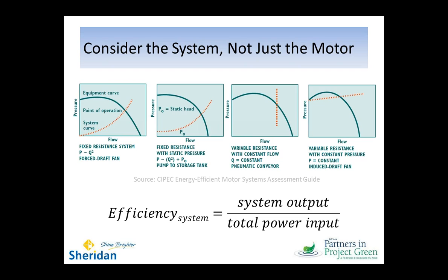The second principle is that we must consider the system and not just the motor. The thing we find is that each system has a system curve, or a description of how it operates. And in these graphs, the system curve is the red line. The red line in the first box is showing us an application where as flow increases, pressure increases. In the second, we basically have a static pressure, so that even with no flow, or very low flow, there's a little pressure in the system. And then we have a variable flow and pressure. Then in the third case, we are maintaining flow at a constant level and pressure varies up and down. And finally, one where pressure is relatively constant at all flow levels.